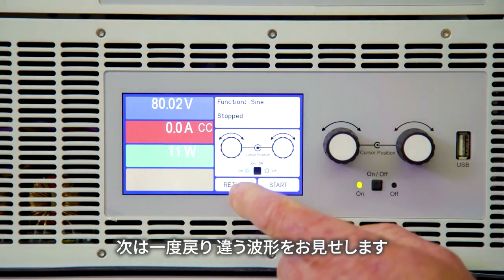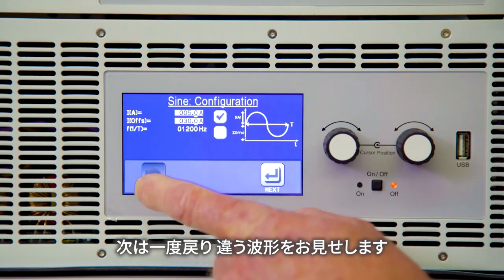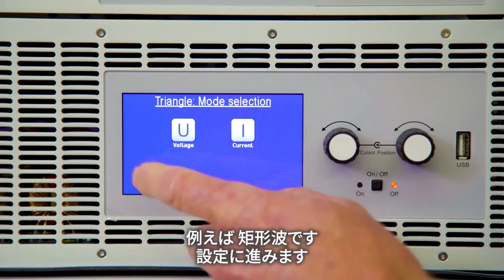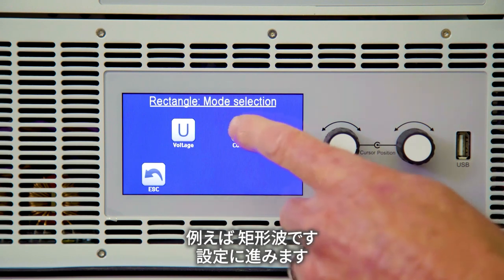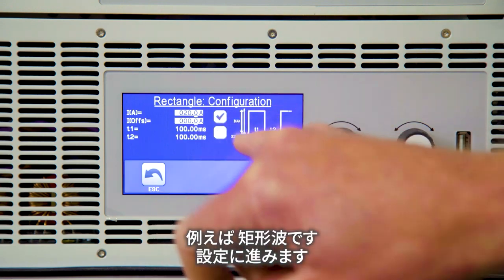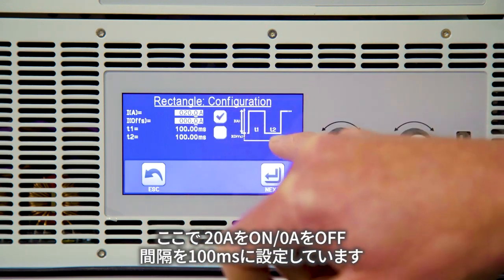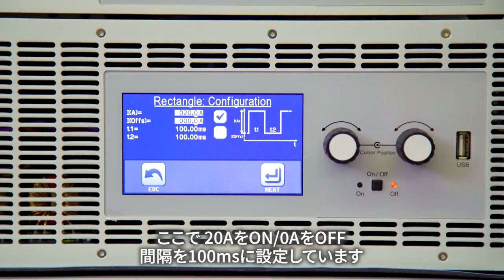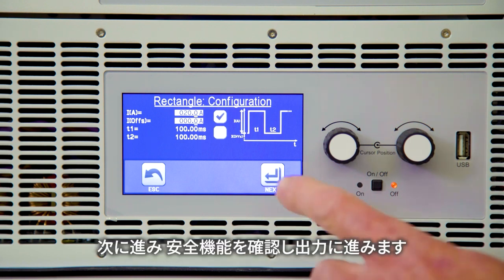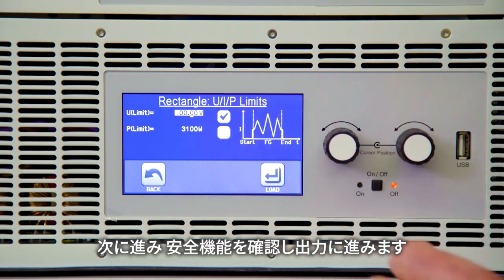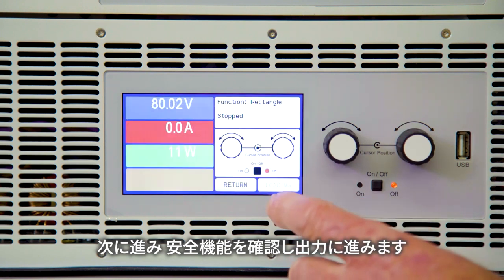Next we'll scroll down and go back. Let's take a look at another feature, which is, for instance, a rectangle. Here I've programmed in 20 amps on and 0 amps off, so you have T1 and T2 programmed. I put both times at 100 milliseconds. We're going to load that in, and again, you have your safety features if you need those as well.